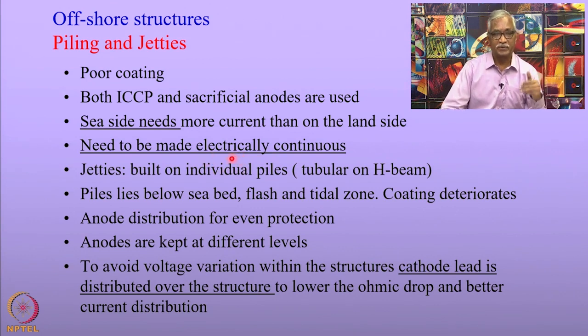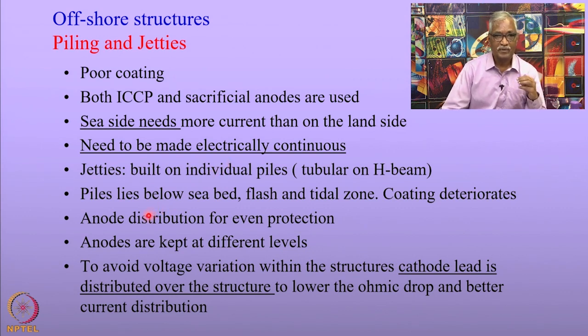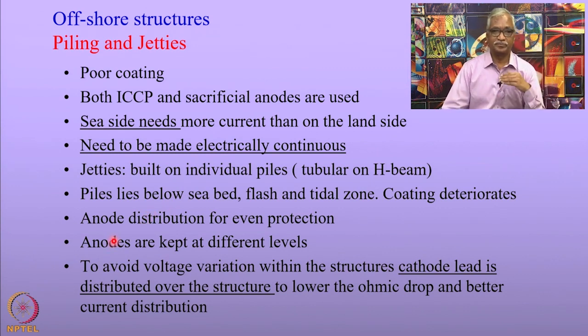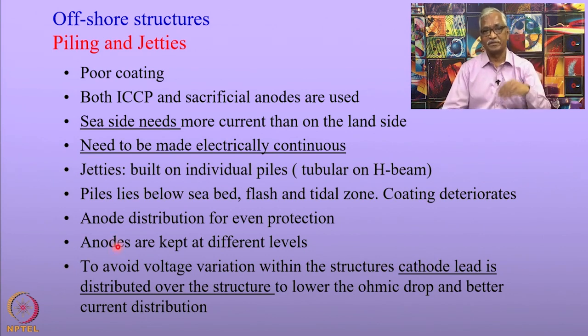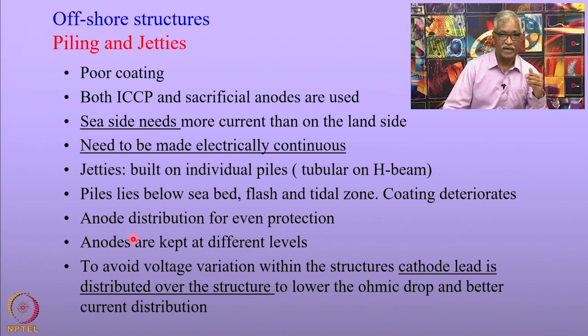If protecting cathodically from onshore, the structure must be electrically shorted so that current flows. If you have structures offshore, the anodes need to be kept at different levels so that the current is uniformly distributed in the structures. Anode distribution is very important for even distribution of current and therefore even protection of the structures.